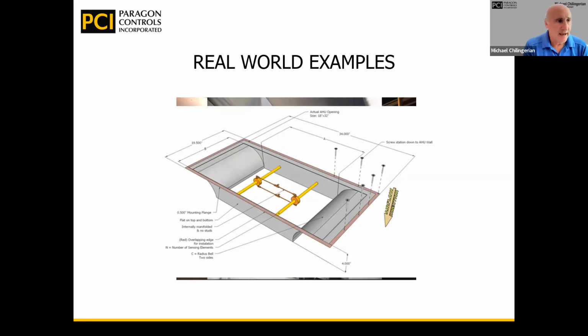I know that the guys up in Albuquerque were doing a school, and there were a number of units, but one of the units happened to have the entrance to the outside air in the direction of airflow from the wind on a regular basis, and they were getting some issues. Well, the reason we were able to solve that problem fairly easily at the minimum airflows is because we make sure that we keep the velocities up a little bit, and we can also tune the transducers. So whether it's a new unit or an outside or a retrofit, we can take those areas, even if they're oversized, and reduce them with a bell mouth design like this that pretty much drops right into place for a unit, and we can give you better accuracy by keeping the velocities up. And these products have basically a thousandth of an inch pressure drop, so it's not going to be an issue for your existing system.